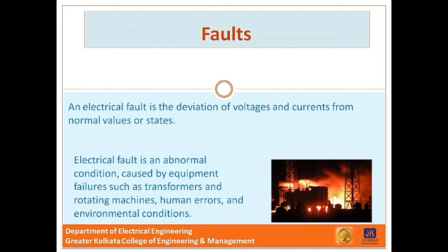Electrical faults are caused by equipment failure such as of a transformer, generator or motor, or they may be caused by human error, or by environmental conditions like lightning. So from this discussion, you have a clear idea why faults are important in a power system. Fault detection and analysis are necessary to select or design suitable switchgear equipment like relays, circuit breakers, fuses or other protective devices.